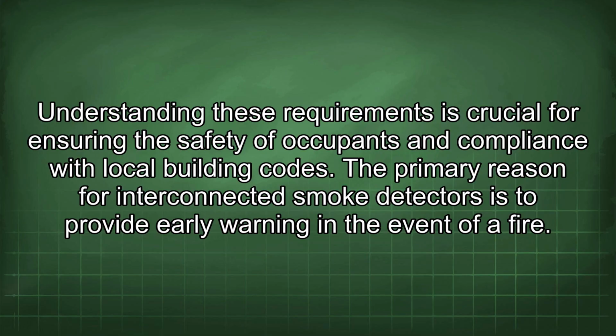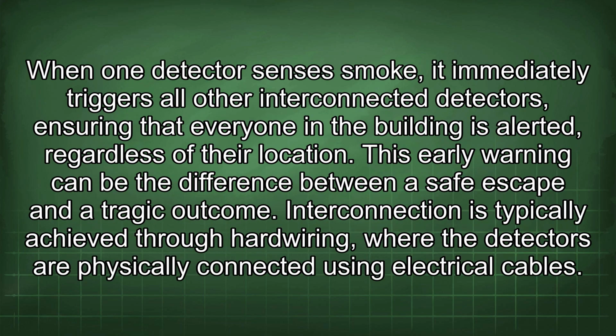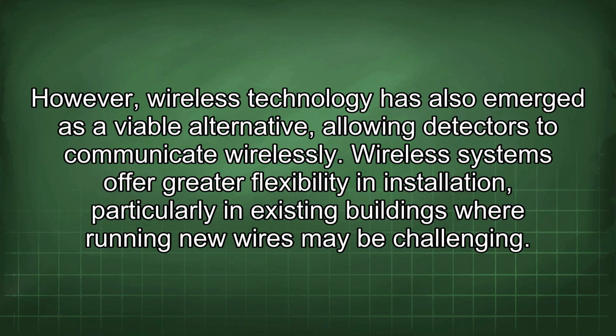The primary reason for interconnected smoke detectors is to provide early warning in the event of a fire. When one detector senses smoke, it immediately triggers all other interconnected detectors, ensuring that everyone in the building is alerted, regardless of their location. This early warning can be the difference between a safe escape and a tragic outcome. Interconnection is typically achieved through hardwiring, where the detectors are physically connected using electrical cables. However, wireless technology has also emerged as a viable alternative, allowing detectors to communicate wirelessly. Wireless systems offer greater flexibility in installation, particularly in existing buildings where running new wires may be challenging.